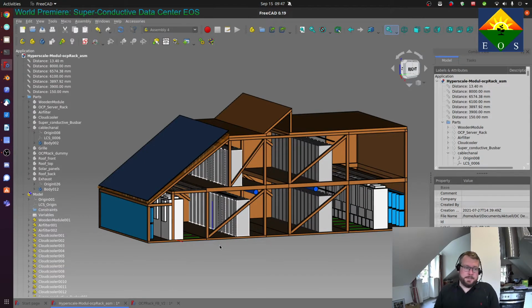And by eliminating AC in the complete data center, we don't have AC-DC rectifying, we don't have losses, we have a lossless busbar, we don't have losses in transport of energy, and we also don't have the power shelf itself, which combined is the last inefficiency standing within a data center, usually quite overlooked in the PUE analysis. We have managed to build this out quite nicely.